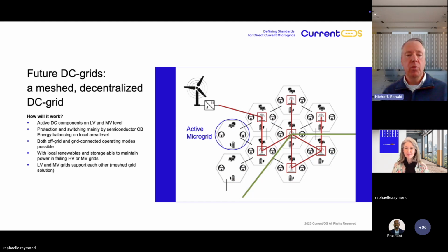So how will future DC grids work? There are a lot of active DC components on low voltage and medium voltage level, and protection and switching is mainly done by semiconductor circuit breakers, as said before, and there is balancing on local level that is done in the active microgrid, as you can see in the blue circle. There are small microgrids which work independently from other energy provisions and independently from the medium voltage and high voltage.